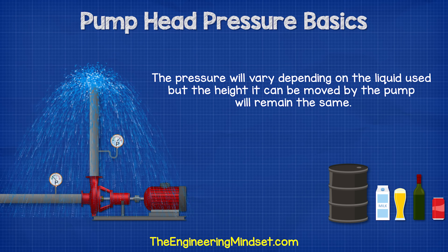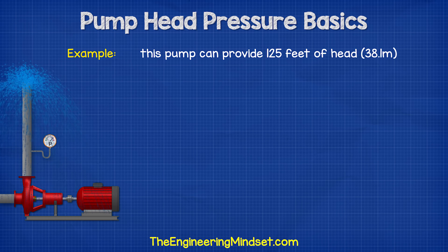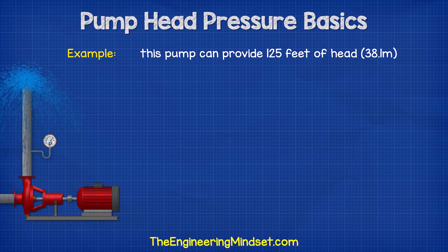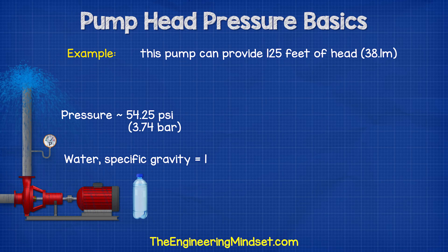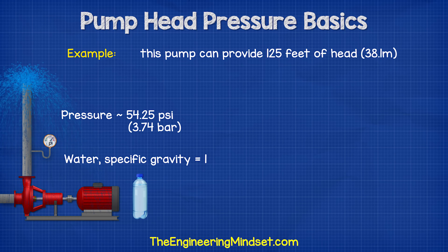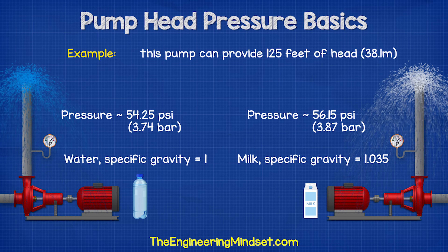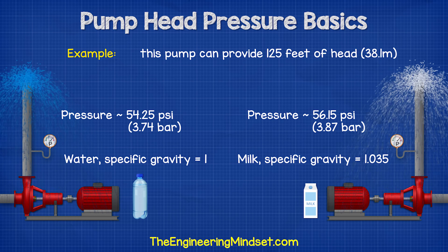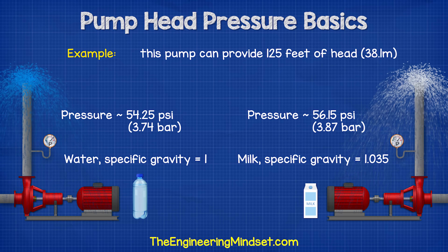However, the height the liquid can be moved by the pump will remain the same. For example, we have a pump which can provide 125 feet of head. If we use it to pump water, the pressure will be around 54.25 psi. But if we were to use it to pump milk, then the pressure will be around 56.15 psi, and that's purely because of the properties of the two fluids.